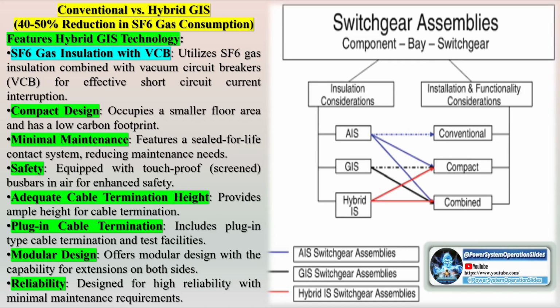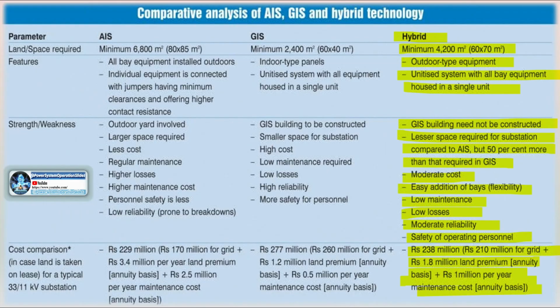When subjected to high-pressure conditions during electrical discharges, pure SF6 can dissociate and form toxic byproducts. Over recent decades, the extensive use of SF6 in the electrical grid has significantly contributed to its increasing atmospheric concentration. SF6 is a potent greenhouse gas with a high global warming potential, and its presence in the Earth's atmosphere is rapidly rising. Without proper disposal methods, all SF6 produced will eventually end up in the atmosphere, necessitating new policies for safe handling and component design, such as the use of hermetically sealed equipment and alternative gas mixtures, to ensure both personnel safety and long-term environmental protection.